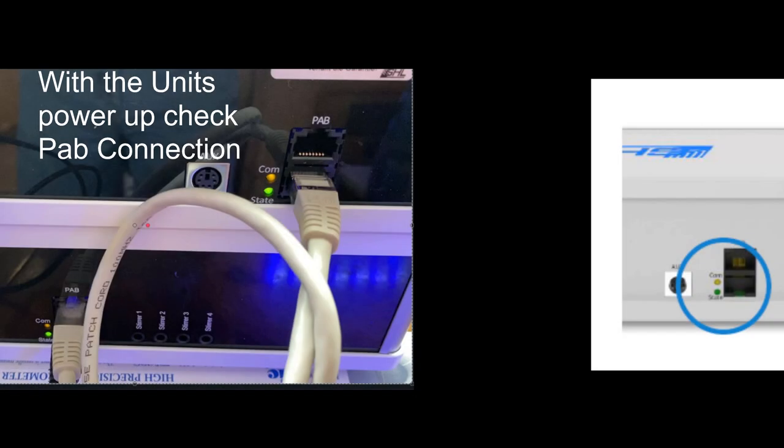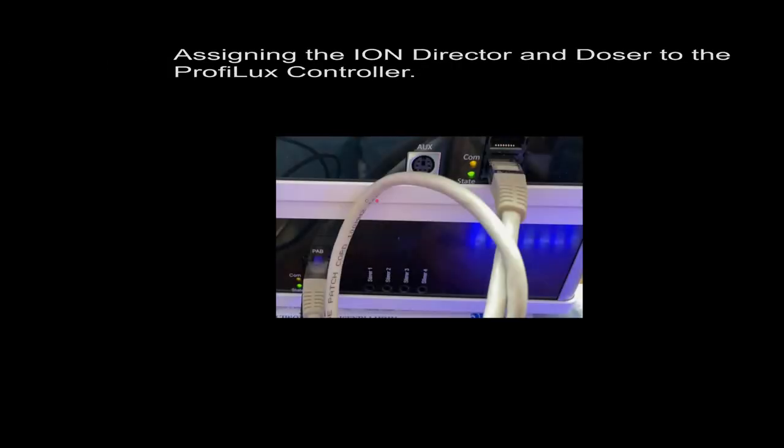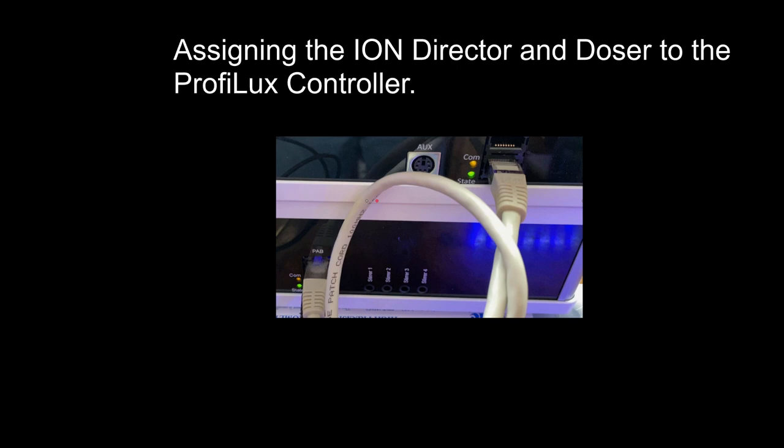With the units now powered up, make sure that communication between the ProfiLux controller and the Ion Director and doser is working. Look on the back of the units for the communications and state light. If these lights are not lit up, power down the units, reconnect the cables, and try again. With both devices on and connected successfully via PAB cable, we need to assign them to the ProfiLux controller.